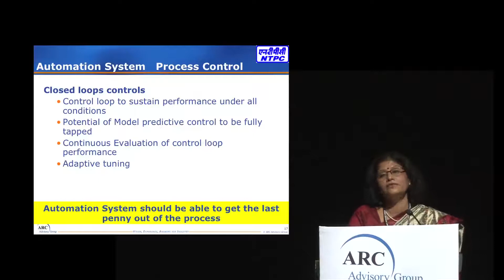For continuous evaluation of such tuning parameters, we provide software in our power plants, for example auto-tune, triage, etc. But still, a knowledgeable person is key. For that, the DCS supplier must develop a pool of specialized persons for this important area and ensure successful commissioning of this loop, which is a very important milestone in this value chain.